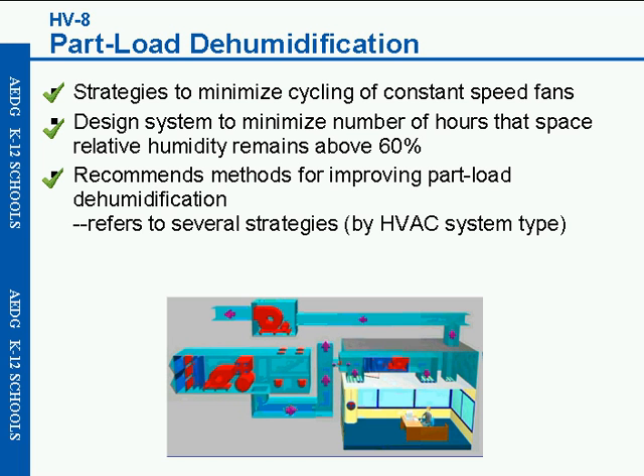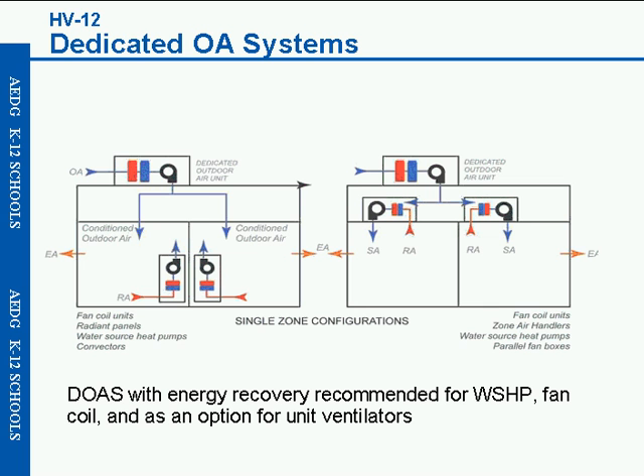One of those recommended system types, or ways to reduce part load dehumidification, is a dedicated outdoor air system, which is recommended for the water source heat pump system type, the fan coil system type, as well as an option for unit ventilators.